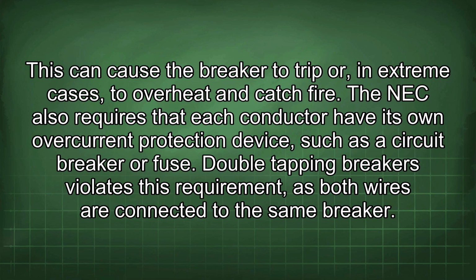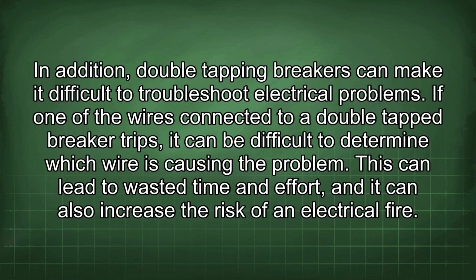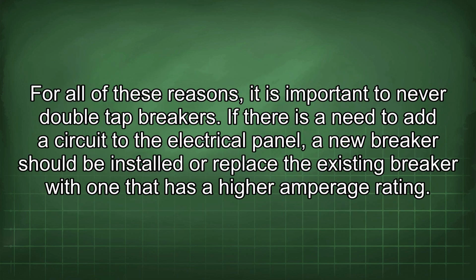The NEC also requires that each conductor have its own overcurrent protection device, such as a circuit breaker or fuse. Double tapping breakers violates this requirement, as both wires are connected to the same breaker. In addition, double tapping breakers can make it difficult to troubleshoot electrical problems. If one of the wires connected to a double tap breaker trips, it can be difficult to determine which wire is causing the problem. This can lead to wasted time and effort, and it can also increase the risk of an electrical fire. For all of these reasons, it is important to never double tap breakers.